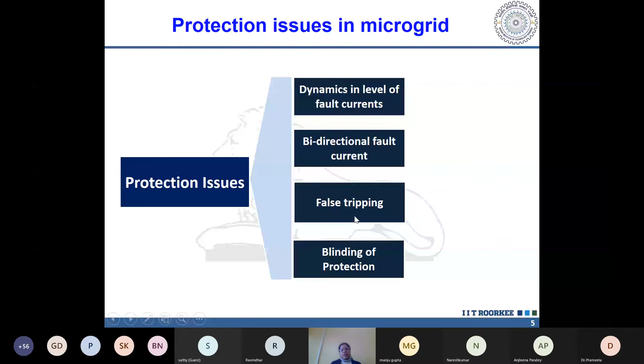So then we have taken up these issues. The second issue is bi-directional fault current. The third one is false tripping, and the fourth one is blinding of protection. Let us understand each issue properly, so that it will be interesting.